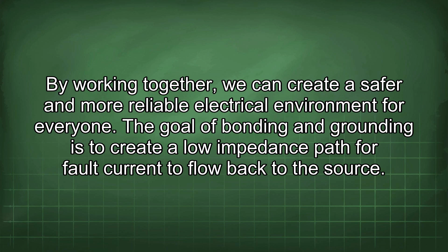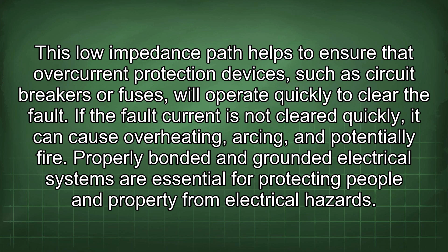The goal of bonding and grounding is to create a low impedance path for fault current to flow back to the source. This low impedance path helps to ensure that overcurrent protection devices, such as circuit breakers or fuses, will operate quickly to clear the fault. If the fault current is not cleared quickly, it can cause overheating, arcing, and potentially fire. Properly bonded and grounded electrical systems are essential for protecting people and property from electrical hazards.